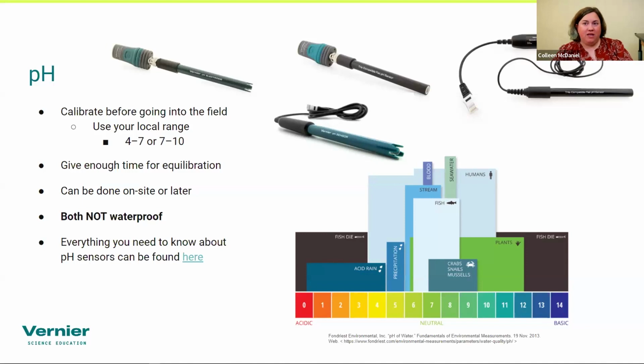One of the important things with pH is making sure to actually calibrate the sensor before you go into the field, because it's going to be a lot easier to calibrate it when you're on campus than it is going to be if you're out stream side. The other thing you want to make sure is that you calibrate it in the appropriate range. So basically you want to know if your water is more on the acidic side or more on the alkaline or basic side. And if it's more acidic, like we're here in Oregon, I would be calibrating my pH sensor between 4 and 7. But as I found out this fall when I was in Kansas City for NSTA, their water is very alkaline. And so for that, I would calibrate my sensor between 7 and 10.